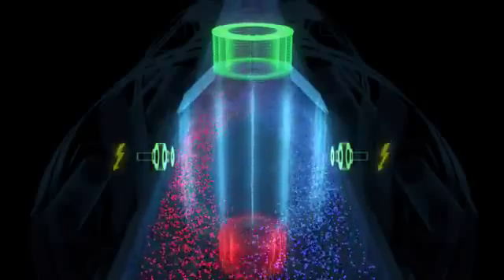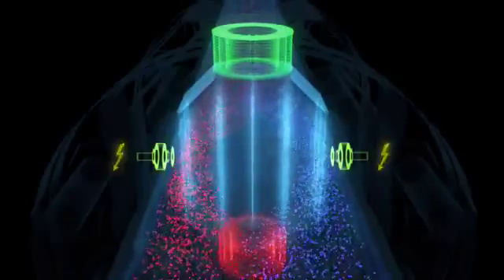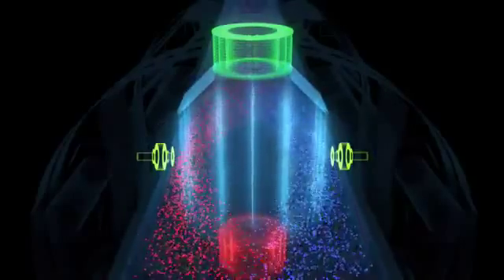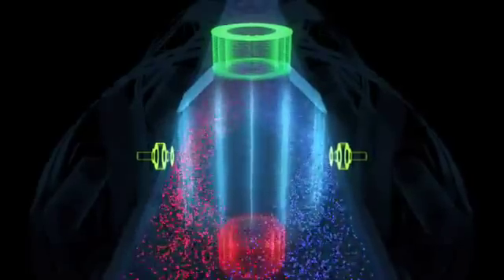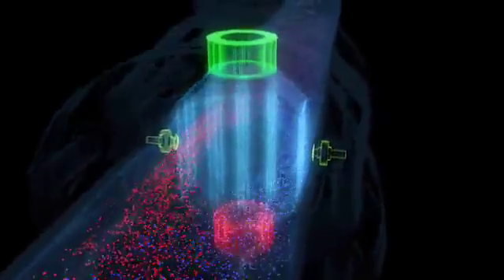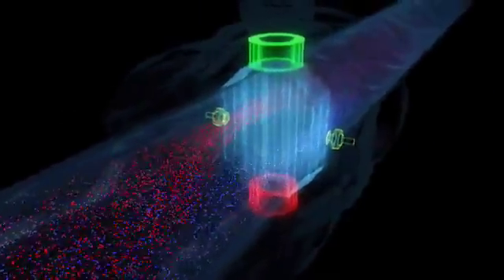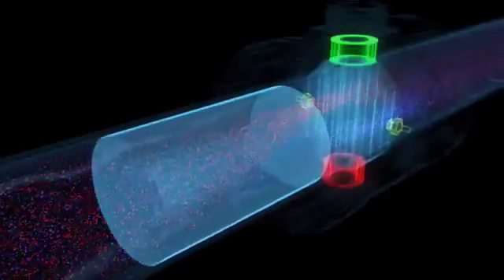Now, an electrical voltage forms, which is detected and measured by the two electrodes. This voltage is directly proportional to the flow velocity in the pipeline. Together with the known tube cross-section, the flow volume can then be calculated. The greater the flow velocity, and thus the separation of the charged particles, the greater the electrical voltage between the electrodes.